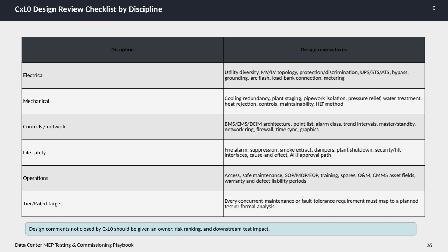Finally, the tier or rated target section emphasizes that every concurrent maintenance or fault tolerance requirement must be linked to a planned test or formal analysis to validate the system's design effectiveness. An important note is that any design comments not closed at this stage should be assigned an owner, given a risk ranking, and have their downstream test impact clearly identified. This approach helps manage outstanding issues proactively and ensures accountability throughout the project lifecycle.